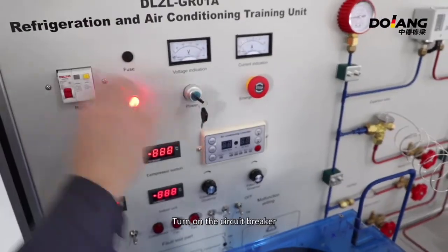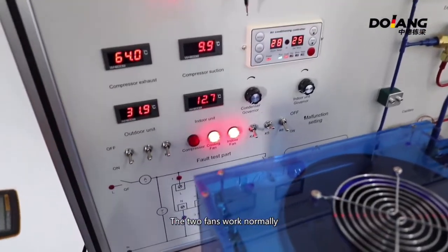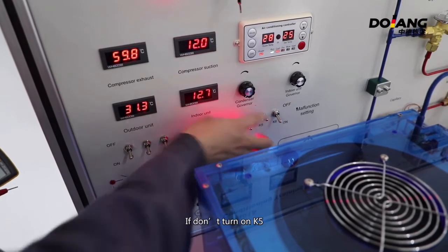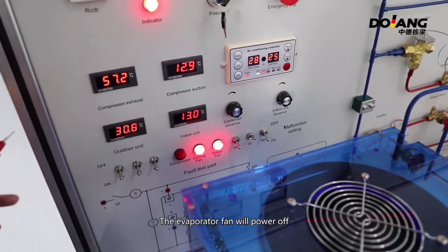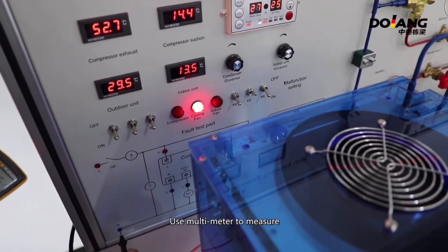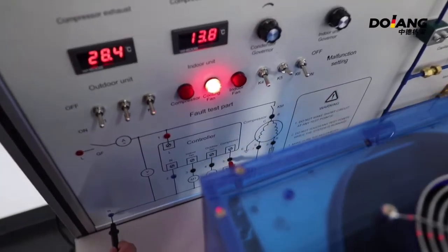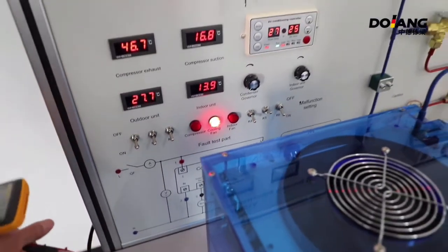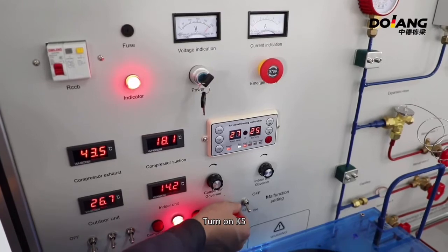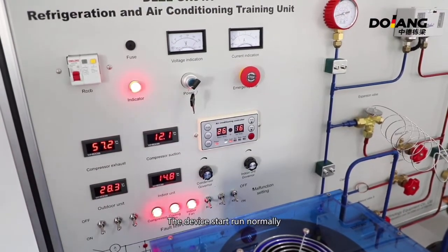Now do the fifth fault experiment. Turn K5 to off, turn on the circuit breaker, turn on the key switch, and turn on the controller. The two fans work normally but the compressor does not run. If the experiment continues for a longer time without turning on K5, the evaporator fan will power off. Use a multimeter to measure — this means it is a compressor fault. Turn on K5 and press the power-on button of the remote controller. The evaporator indicator lights on and the device runs normally again.